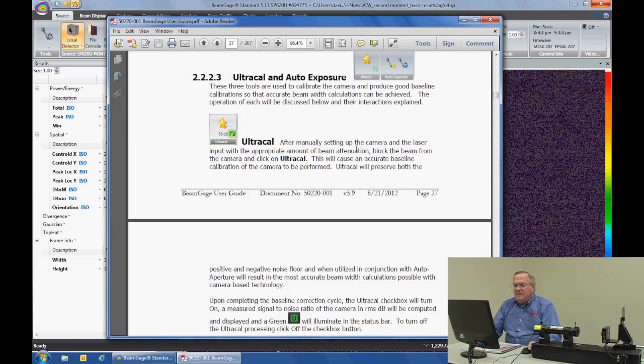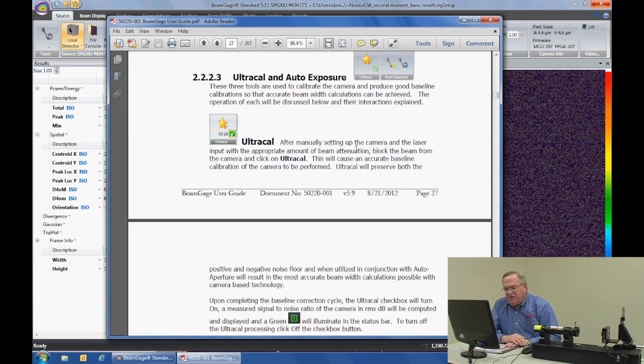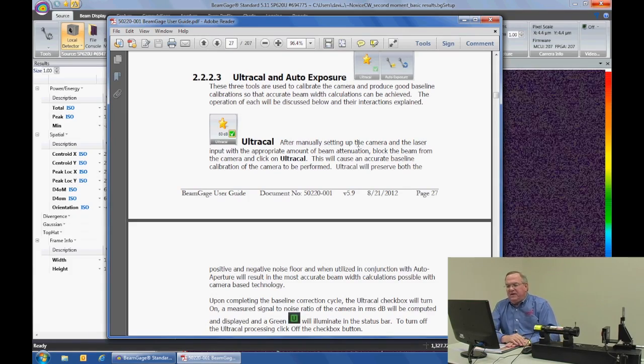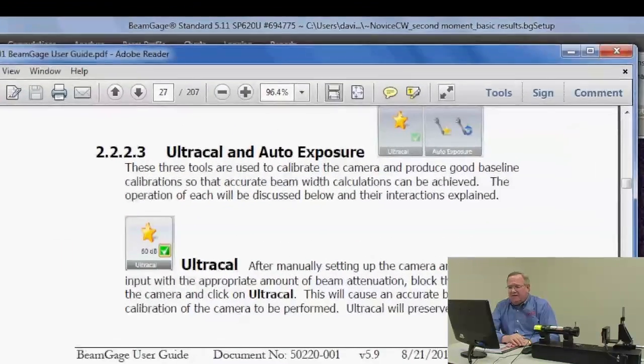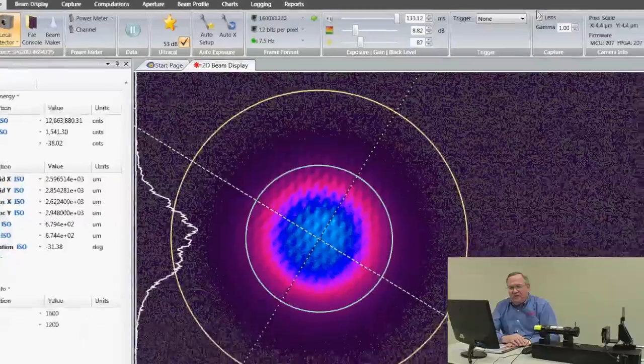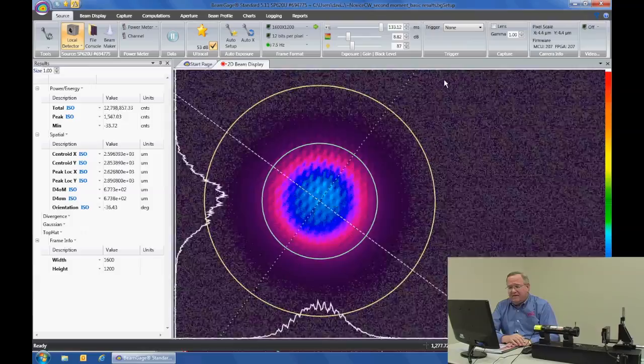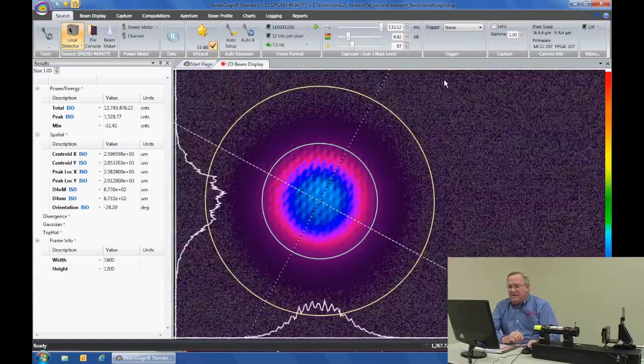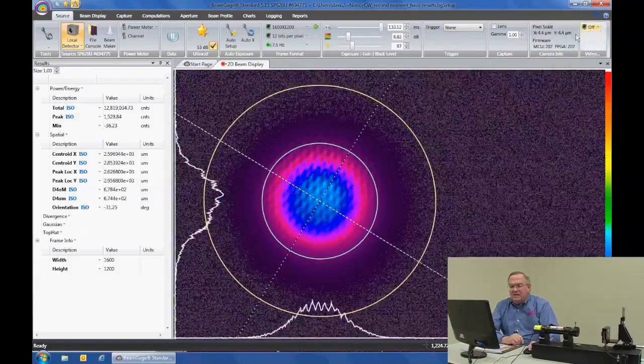In this particular case, the icon took us directly to the page within the service manual for the complete explanation of UltraCal. UltraCal is the major feature that ensures the background is properly baselined to the ambient condition, so your measurements will be accurate within one percent.